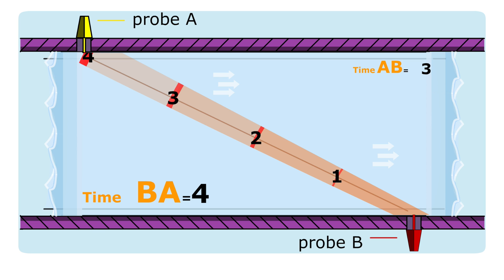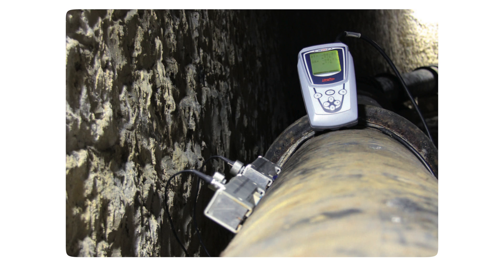Using the difference of the travel times and the physical dimensions of the installation, we get the fluid velocity and the flow rate of the water.